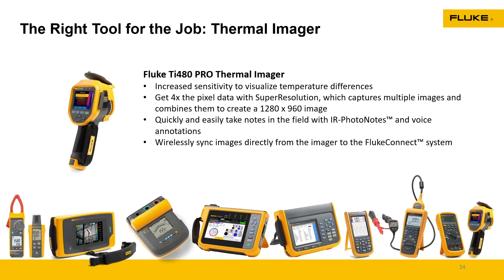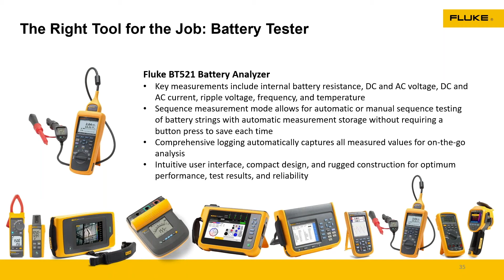Now, we did mention the battery system. You need a battery analyzer as part of that commissioning aspect, to determine your load analysis on it. You can do a study of the batteries prior to commissioning, and then go out and do trending analysis with this as well, determining if that battery capacity is still at 90% or if it's dropped and they need to be replaced. This is a great tool because it allows you to do that analysis.